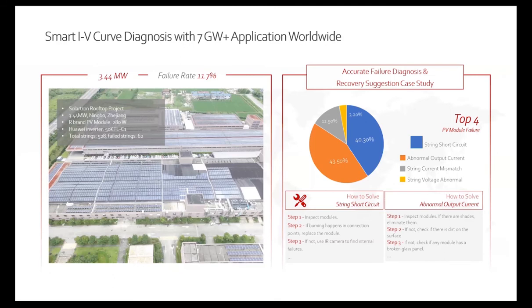So with our 5-year track record now using IV curve diagnostic for well above 7 gigawatts of applications, we can see the top 4 failures that are typically happening with not only our major customers, but you can see here where the customers can improve typically the PV applications, or where the top key failure points are, whether it's in regards to the PV modules or the installation quality.